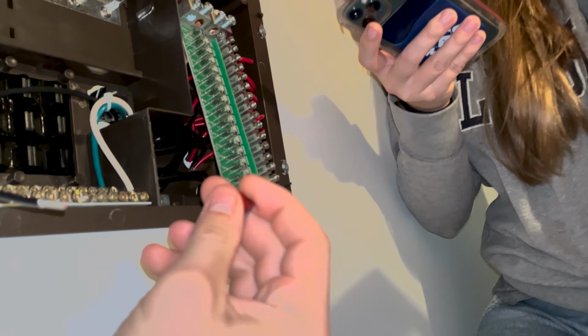Now we are going to start to wire the AC side of the distribution panel. As you can see, the white, green, and black wires have gone through the hole in the back, where they are connected to the inverter. The white wire gets attached to the front of the panel, the green, which is the ground, goes behind that, and the black, which is the live wire, gets attached to the breakers. This is going to be the main breaker, the one that is attached directly to the inverter and controls power to all AC devices.